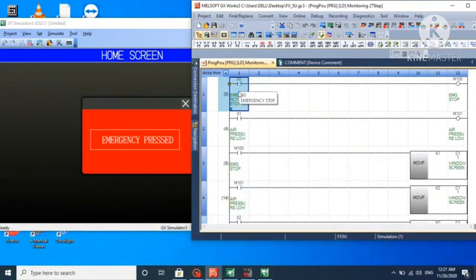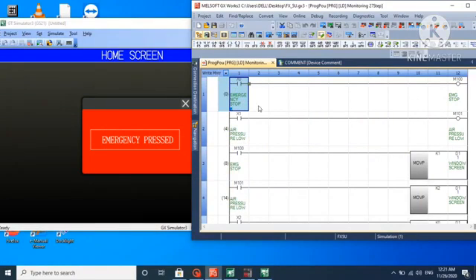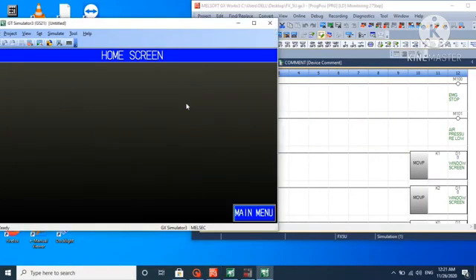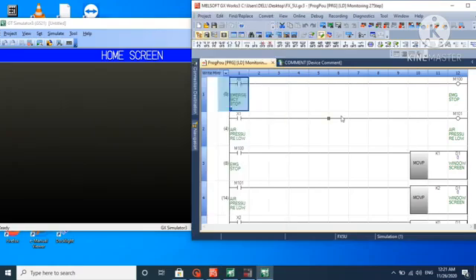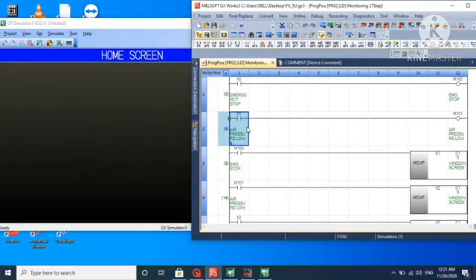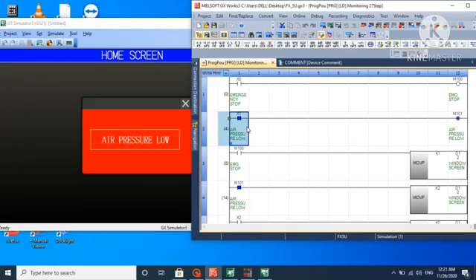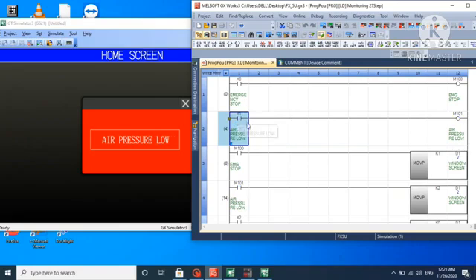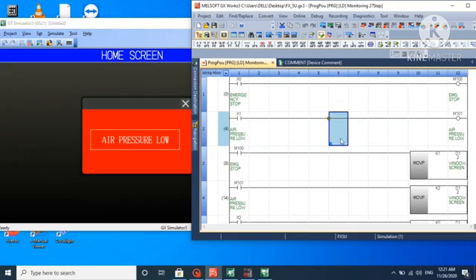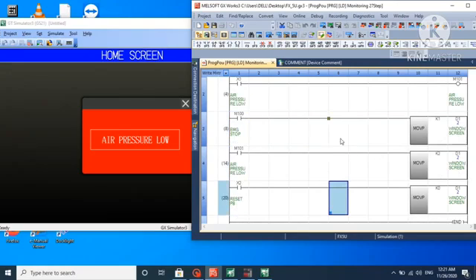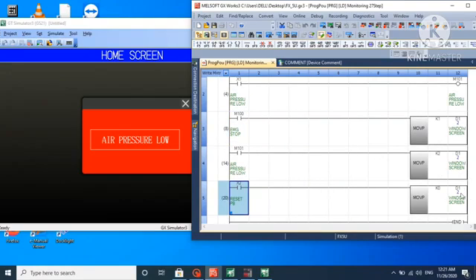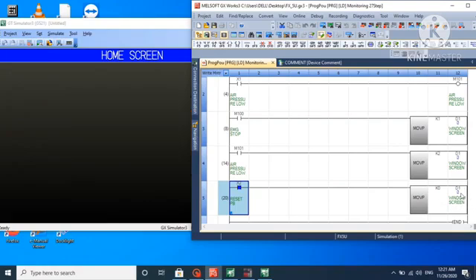I close the window and you can see D1 value is 0. Now I give air pressure low and you can see air pressure low alarm pops up, and the value in D1 is 2. You can directly from ladder reset the PB and move 0 to close the window.